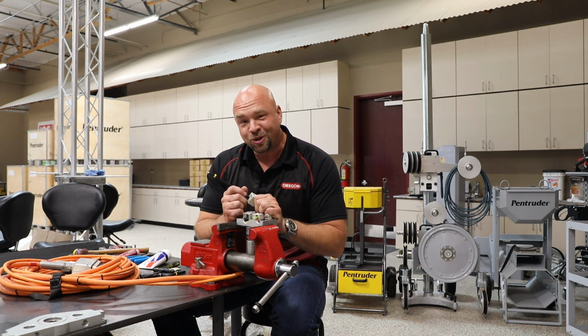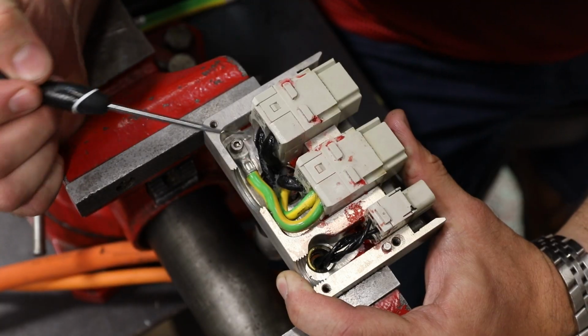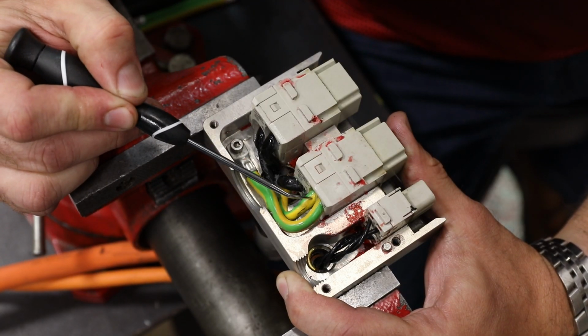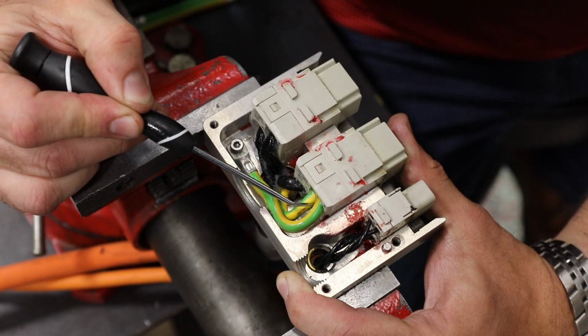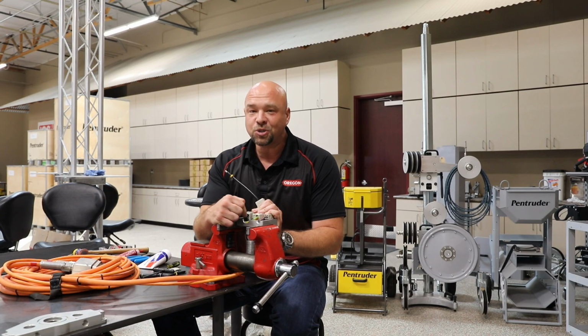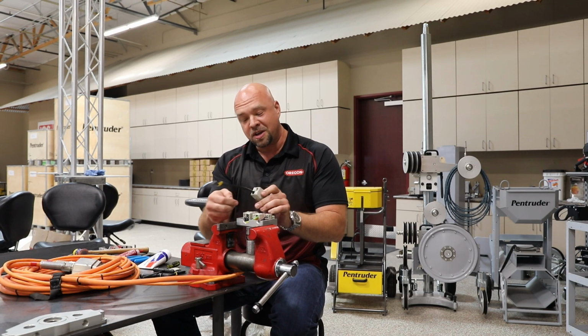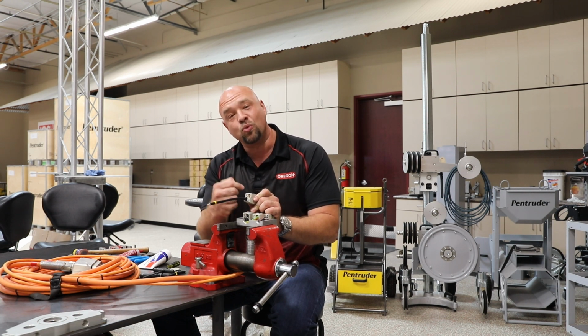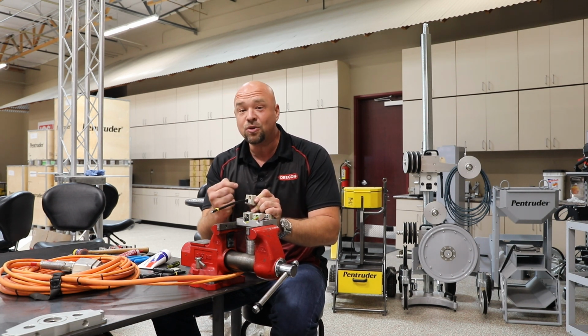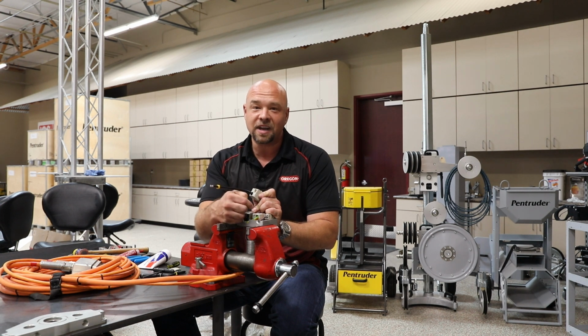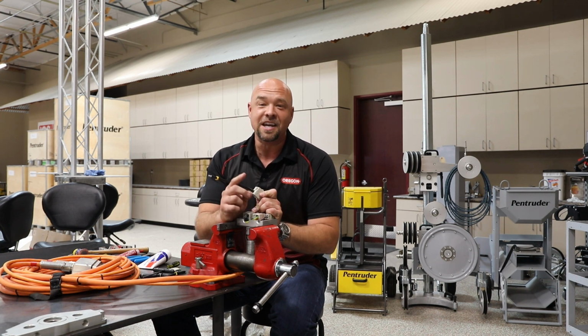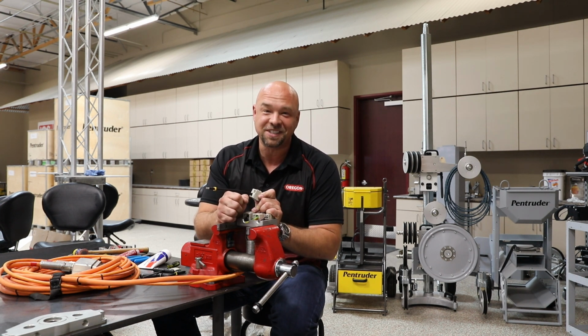Superstar secret: if you notice, we've got an L1, L2, L3, and a ground wire inside this high voltage connector. Make sure they're in the same order. What I recommend is taking one wire out at a time and reinstalling it into the next connector. If you do that, you won't confuse L1, L2, L3, and the ground, and you won't have to send your machine back to the pros to get it working again.